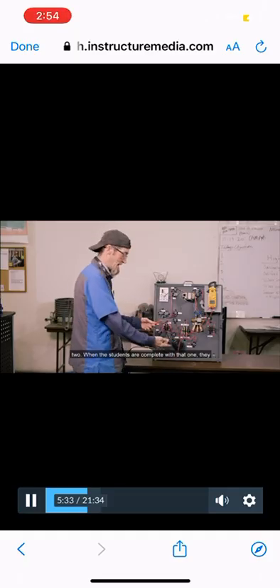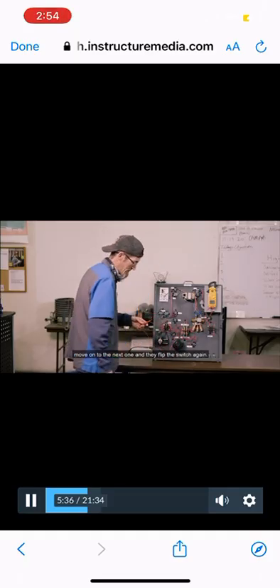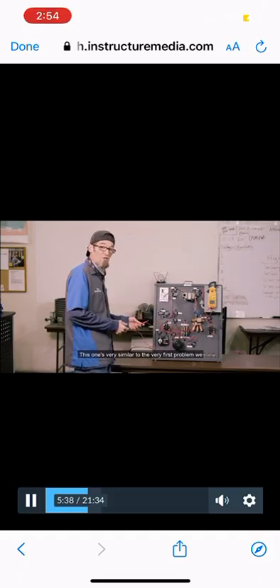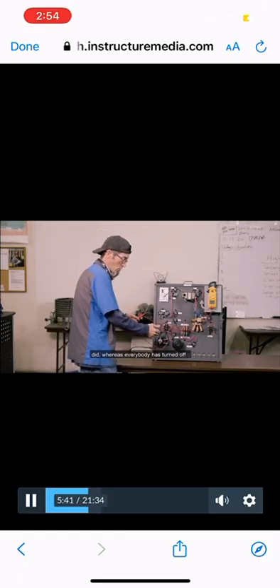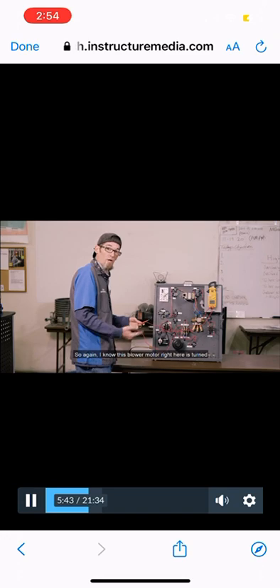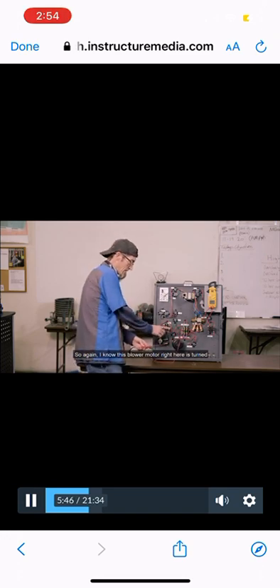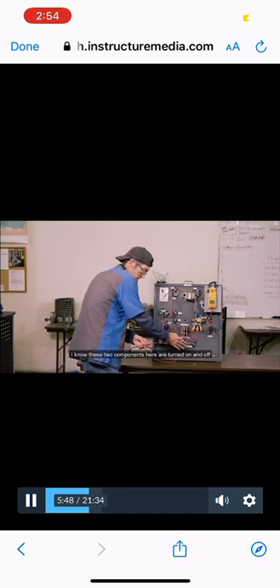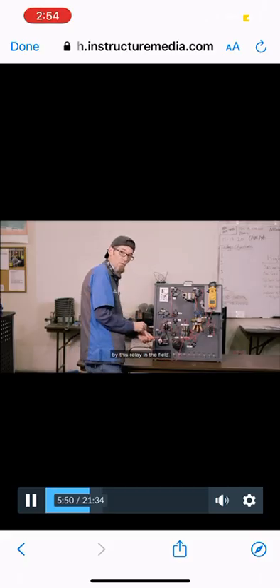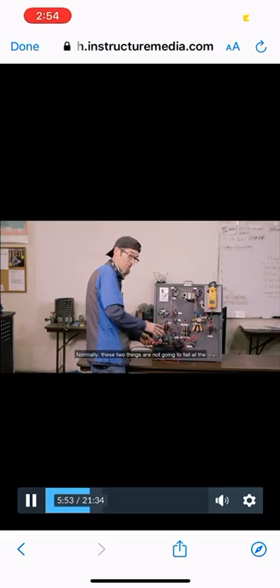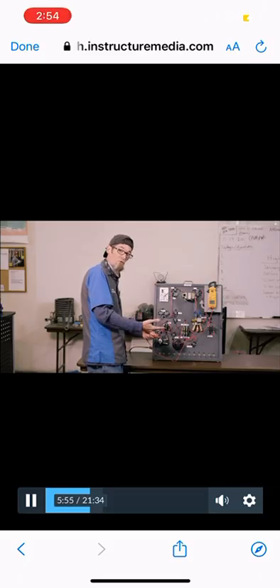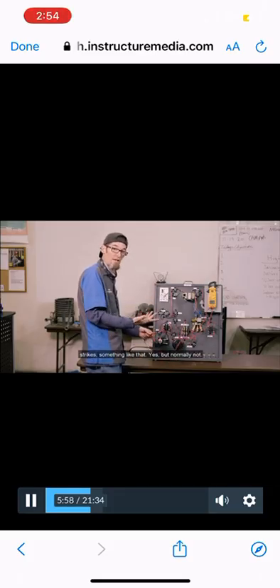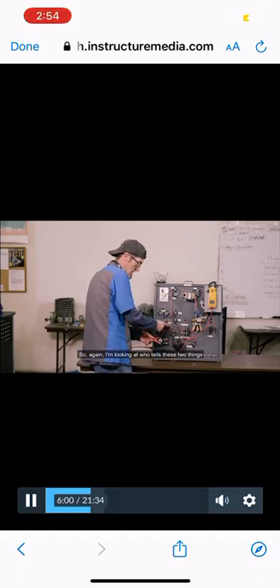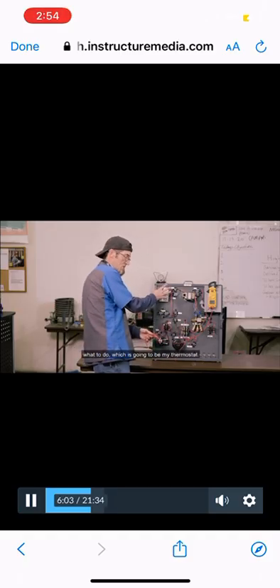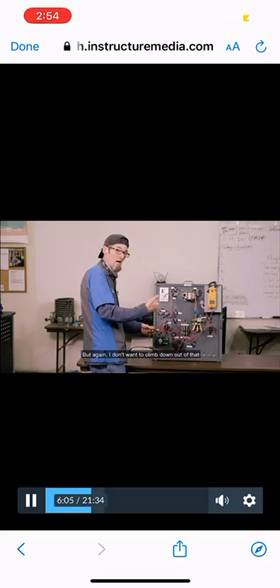When the students are complete with that one, they move on to the next one, and they flip the switch again. This one's very similar to the very first problem we did, where everybody has turned off. Again, I know this blower motor right here is turned on and off by this relay. I know these two components here are turned on and off by this relay. In the field, normally these two things are not going to fail at the same time. Electrical surge, a lightning strike, something like that, yes, but normally not. So again, I'm looking at who tells these two things what to do, which is going to be my thermostat. But I don't want to climb down out of that attic. That's a waste of time and money for you guys and your company.